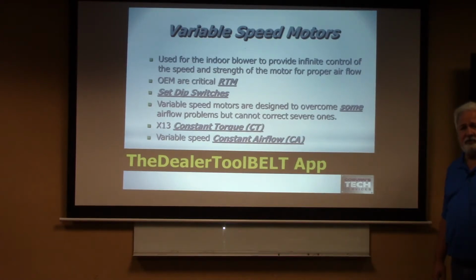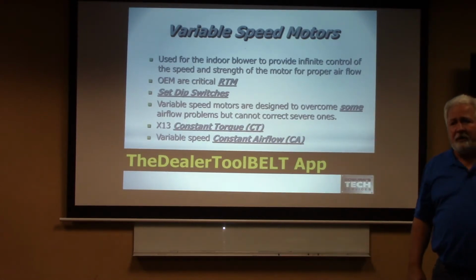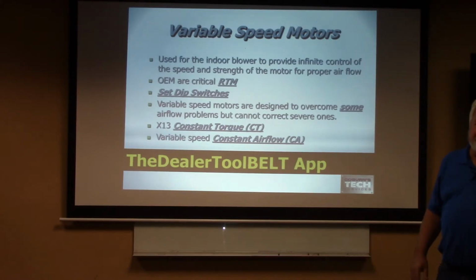Every manufacturer of these motors comes from probably less than 4 manufacturers of motors, and each one of them is going to specify their input information differently. So you can't just take one Regal Beloit motor and replace it with another one, because the software is different from one manufacturer to the other. So the OEM stuff is critical.